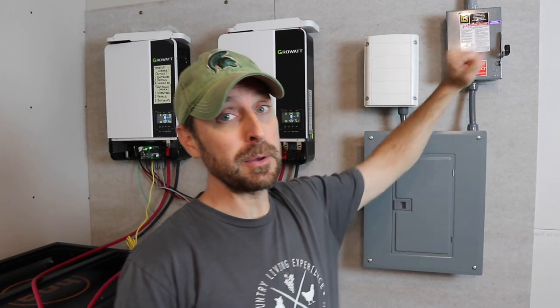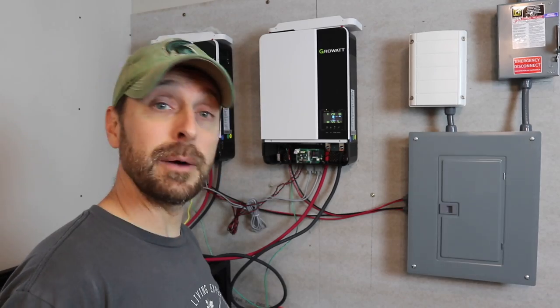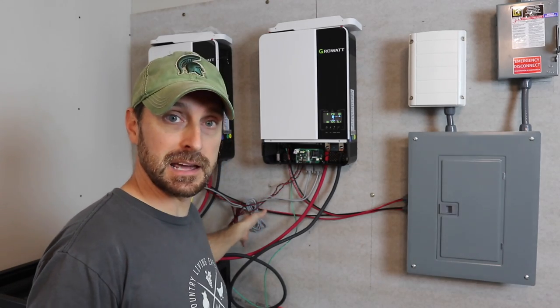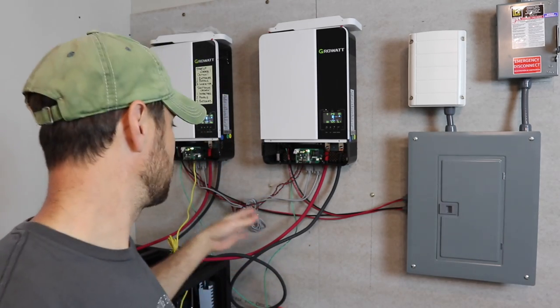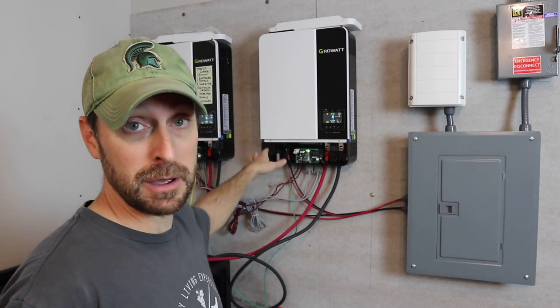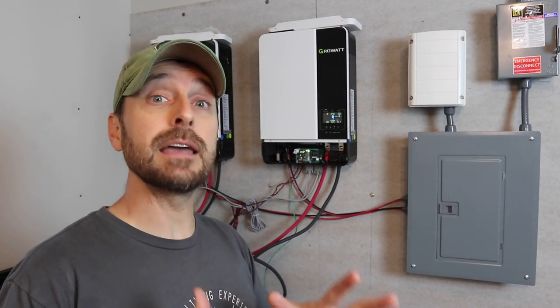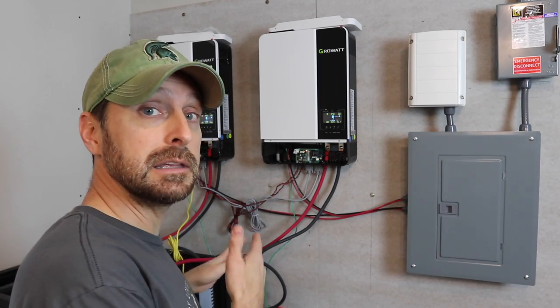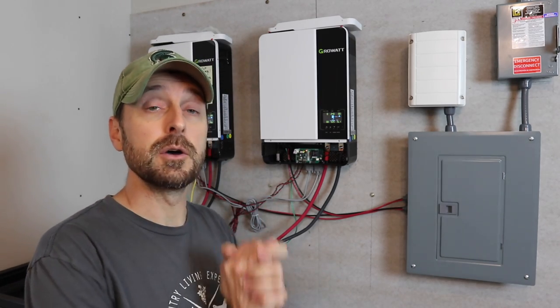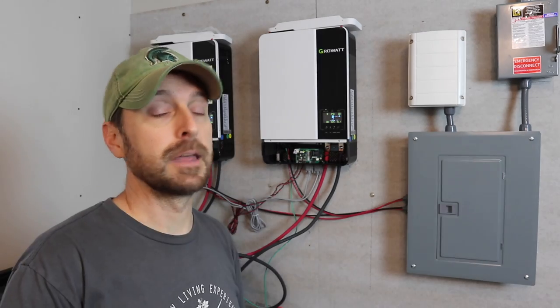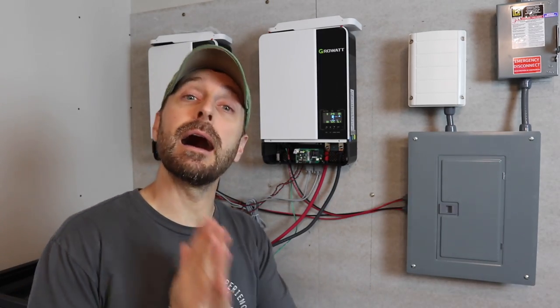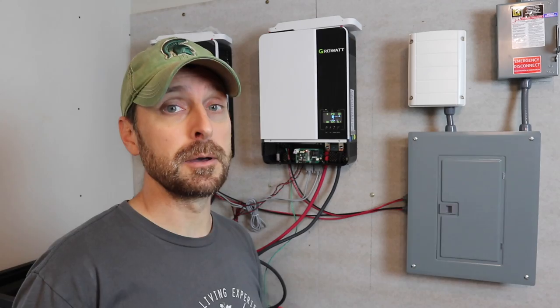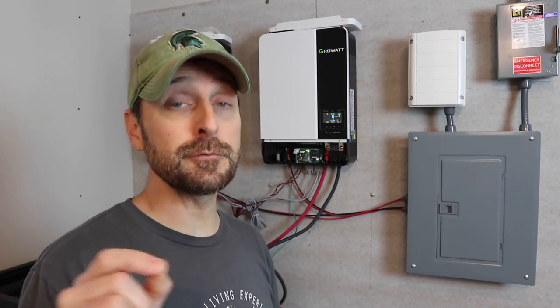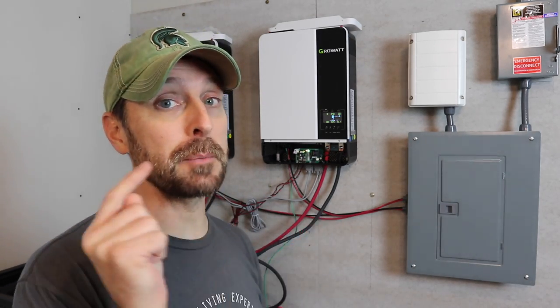So that was a lot to cover in one video. So are we ready to flip over our safety switch and power the house? Not yet. And here's why. I don't have my DC or PV disconnect switch installed right now, and my PV lines are not going into my inverters. So it's recommended that you do not power directly and only from the batteries without having the PV connected. Now, some of you may say, well, it's no problem. Well, I am following the instructions that I was given by Signature Solar. So stay tuned for the video where we flip that switch and start powering our house.